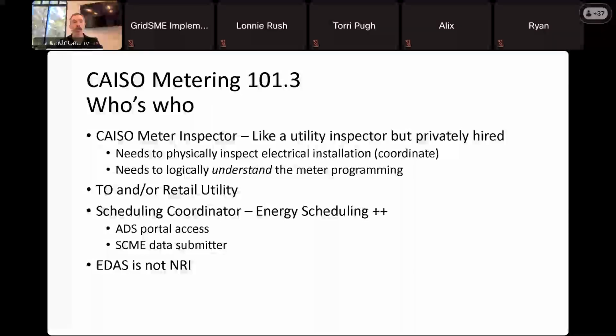The other component of a CAISO meter inspection and the duty of the CAISO meter inspector is to understand the meter program. As I mentioned, these meters that we put in substations are almost 0% analogous to the meters on your house, on the side of a Walmart, in an agricultural field, or wherever else you might find a meter, from a logical implementation perspective. They have a bunch of different industrial protocols where they stream data to other devices. But importantly, unlike any other meter, you're able to intervene with the processing of the meter between its measurement of voltage and current and its recording of energy.